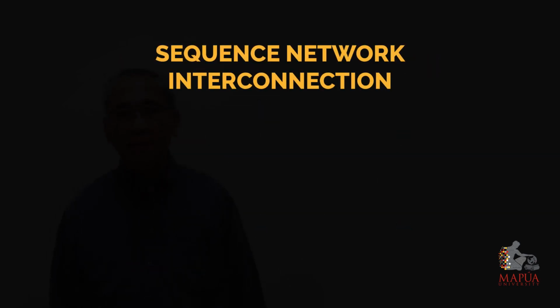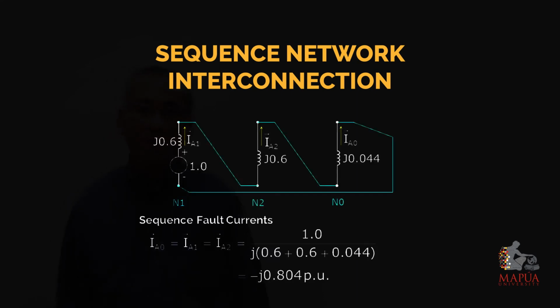Now, how are these three sequence networks interconnected for this single line to ground fault? Notice that the currents flowing, Ia1, Ia2, and Ia0, are equal based on our computation. The interconnection of these three sequence networks will be in series.